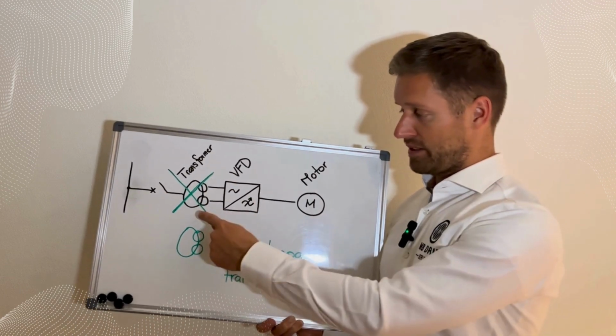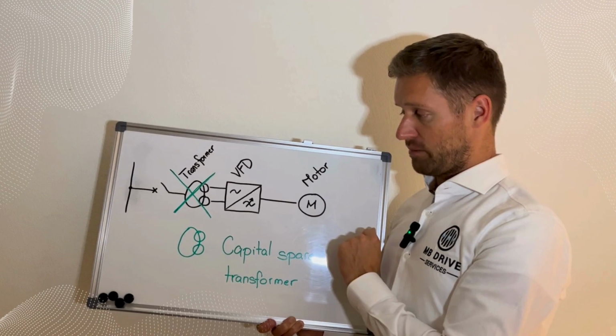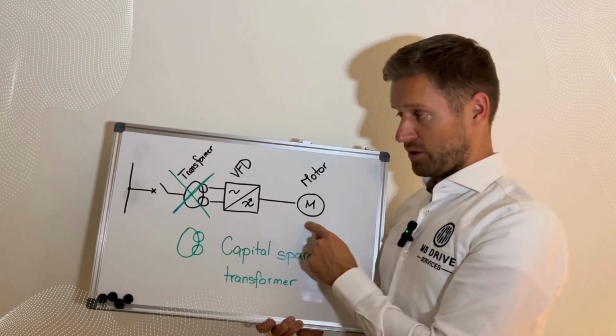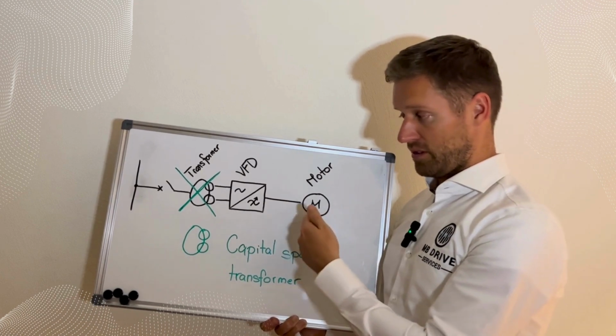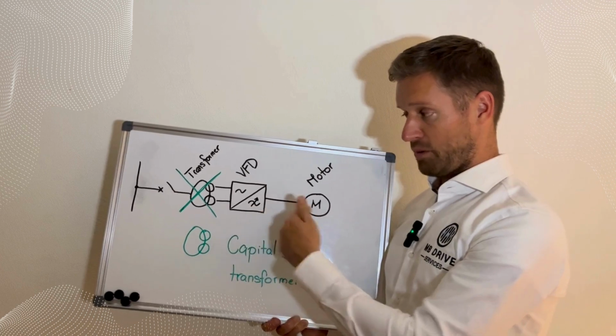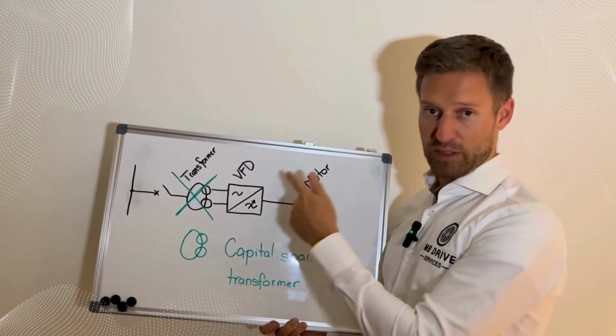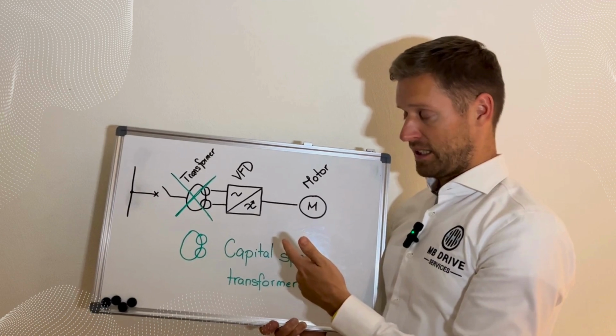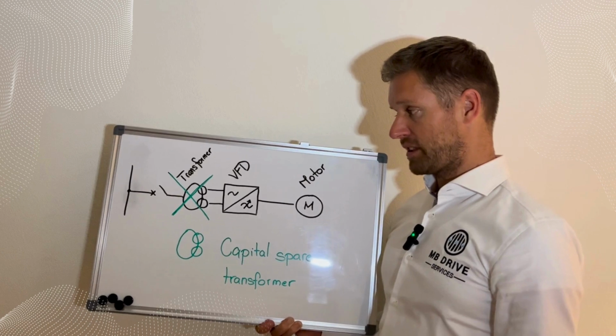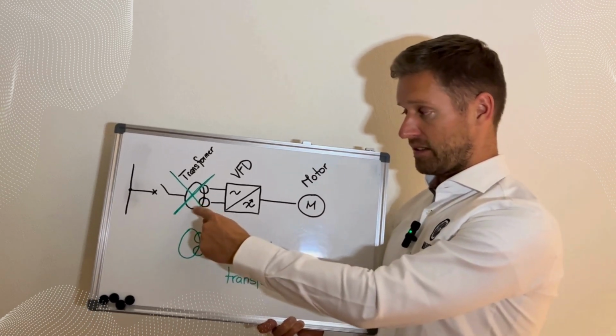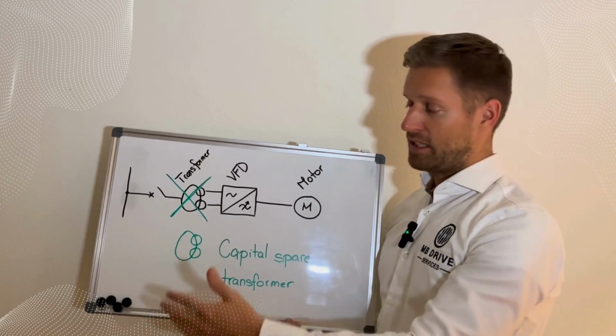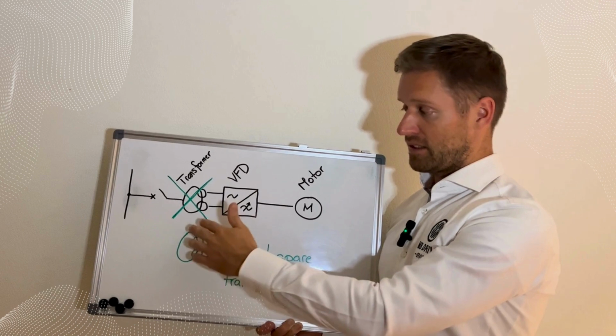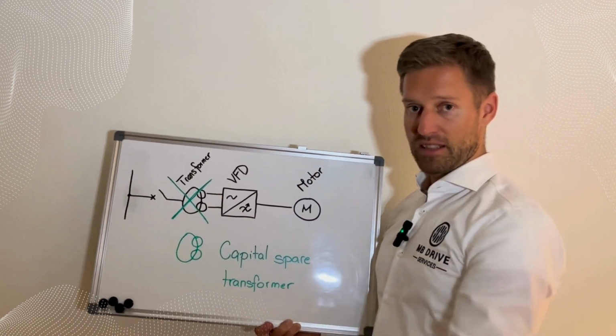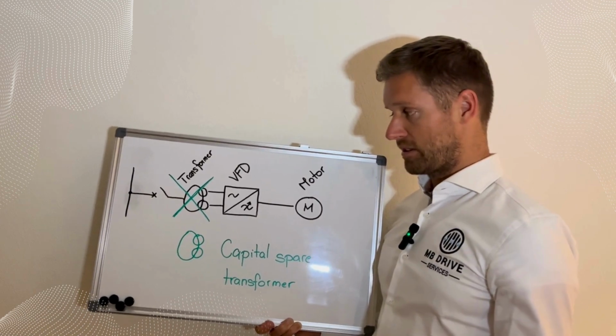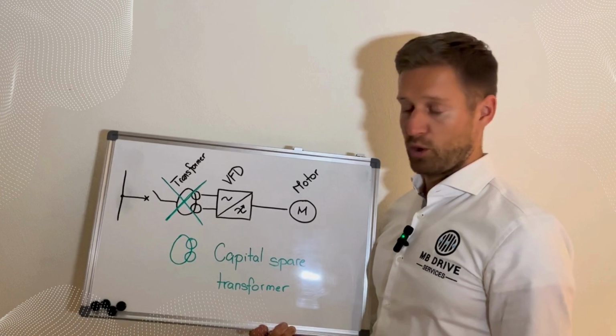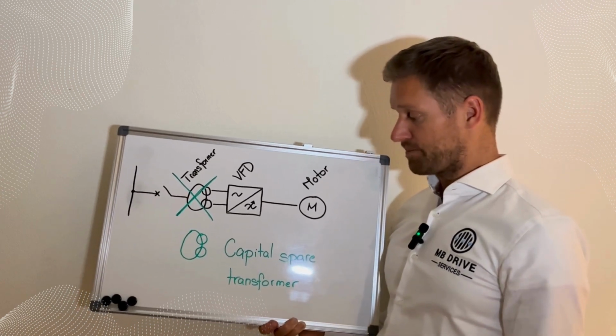And if this transformer is not working, then the whole drive system might be down. Maybe the motor voltage is different than the grid voltage, so you cannot operate it direct online. Or maybe even if the voltages are the same, the motor might not be designed for direct online start. So you can have really severe problem, and the repair can take very long time, especially nowadays. If it would be severe failure and the transformer would not be repairable, nowadays the lead times for a new transformer are really long, 1 year and more. So it can be very severe.